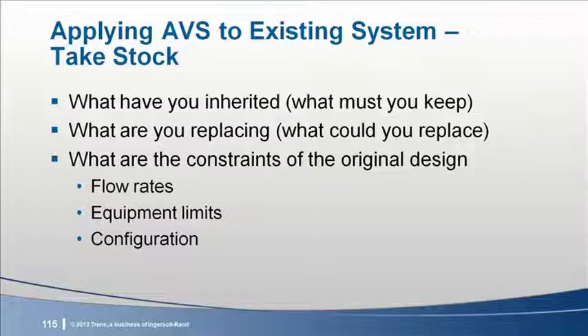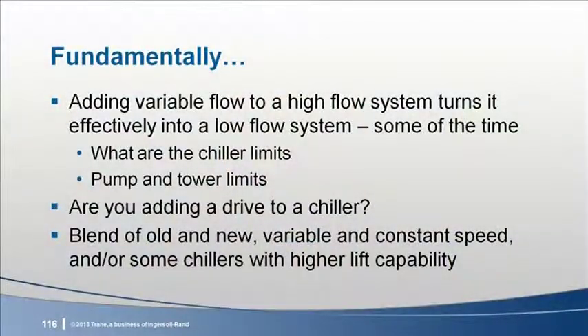What are the constraints of the original design? Do you have the original design in actual operation today? For example, you have 3 chillers in parallel before, but one of them was a swing chiller. Having different sized chillers in an all-variable speed plant complicates things because of the different limits, and I would advise against dynamic condenser flow control in an asymmetric chiller plant. Adding variable flow to a high flow system, for example a 3 GPM per ton system, turns it into a lower flow system at least some of the time. The first constraint you run into as you turn down the condenser water flow, in all likelihood, is a chiller limit. As I said, this is likely the first constraint, but probably not the only one.